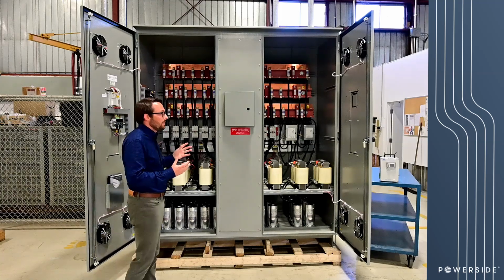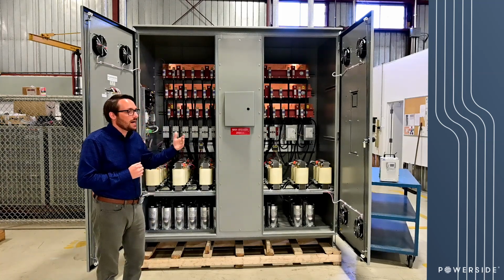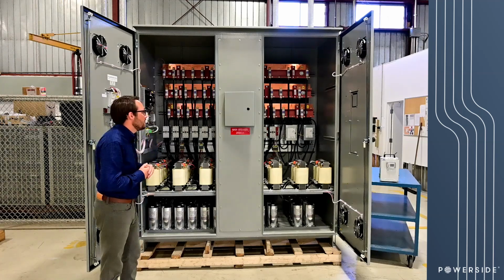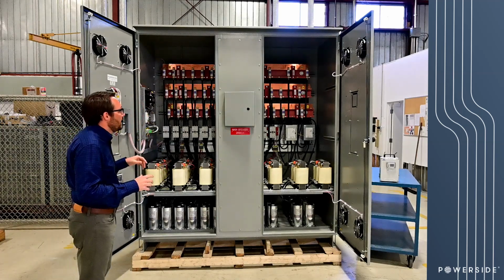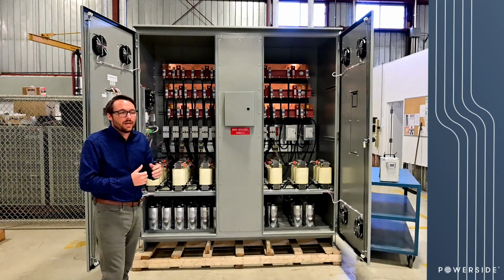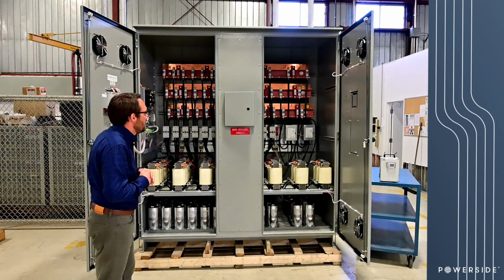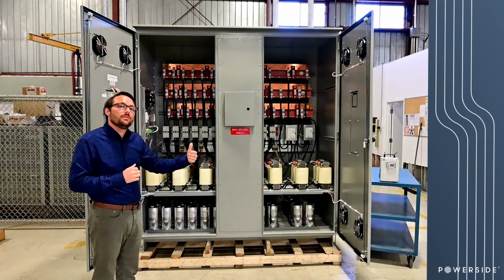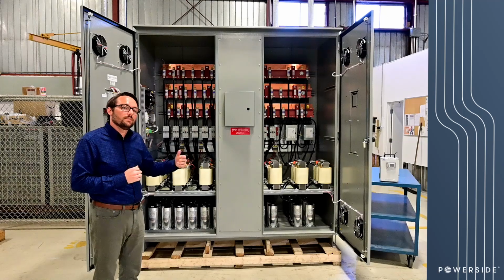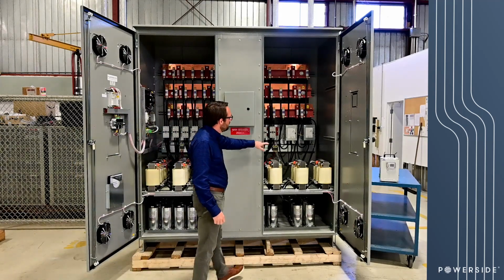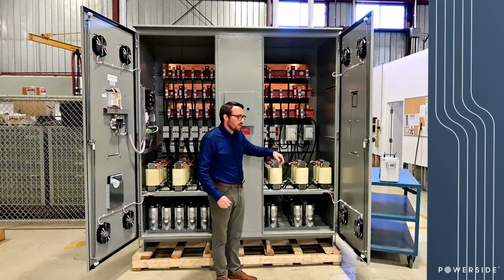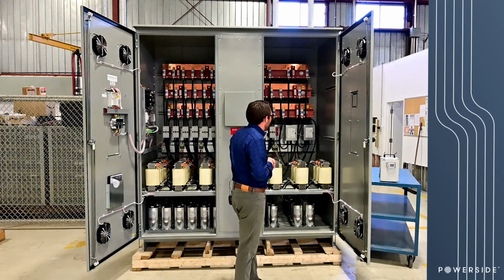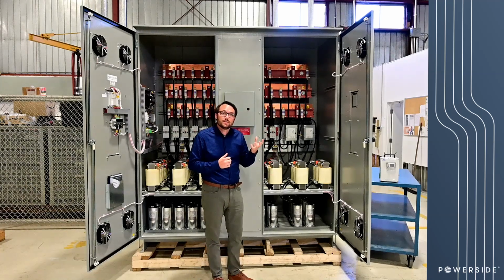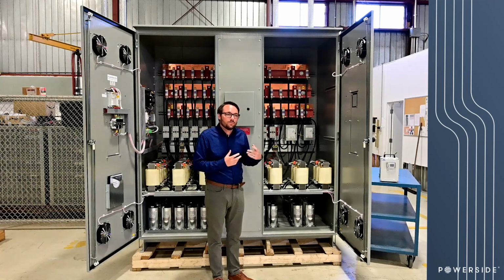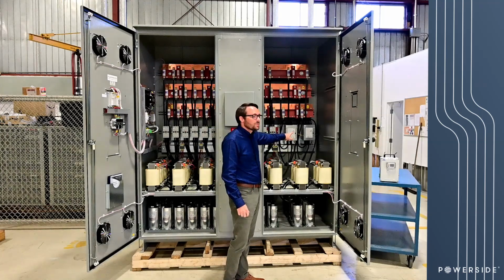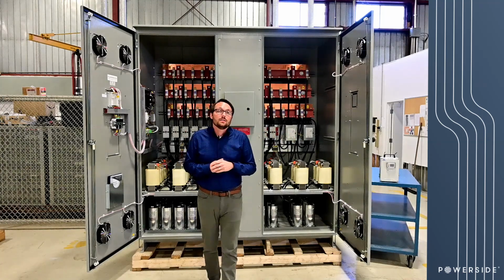Now, one of the things about this particular application is that there was a very high base load that was there. And so this system here is designed, it is 1000 kVAR or 1 megaVAR, depending on your preference. And it's designed with 800 kVAR of contactor switching with the addition of 2 stages that are thyristor switched. And as you saw in that previous image, for the load variability where it increases during the pressing of the billets through the extrusion process, these thyristors can turn on and off in as little as 3 cycles.